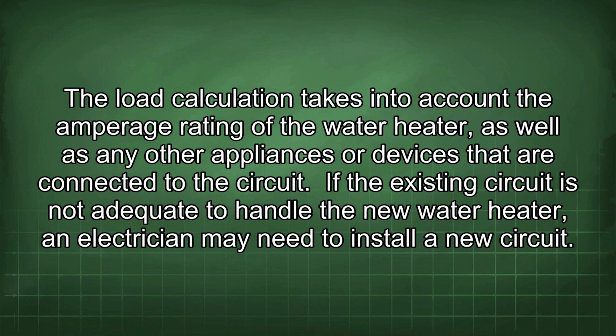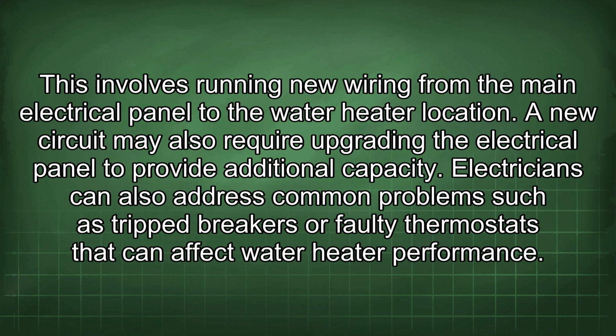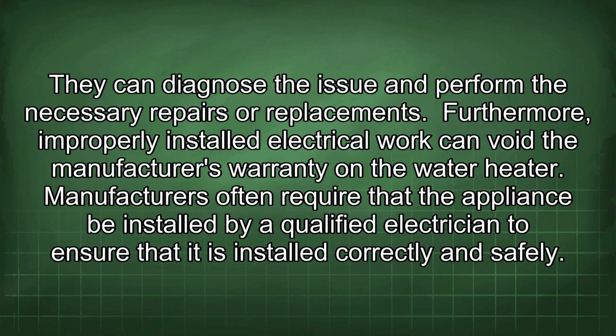If the existing circuit is not adequate to handle the new water heater, an electrician may need to install a new circuit. This involves running new wiring from the main electrical panel to the water heater location. A new circuit may also require upgrading the electrical panel to provide additional capacity. Electricians can also address common problems such as tripped breakers or faulty thermostats that can affect water heater performance. They can diagnose the issue and perform the necessary repairs or replacements.